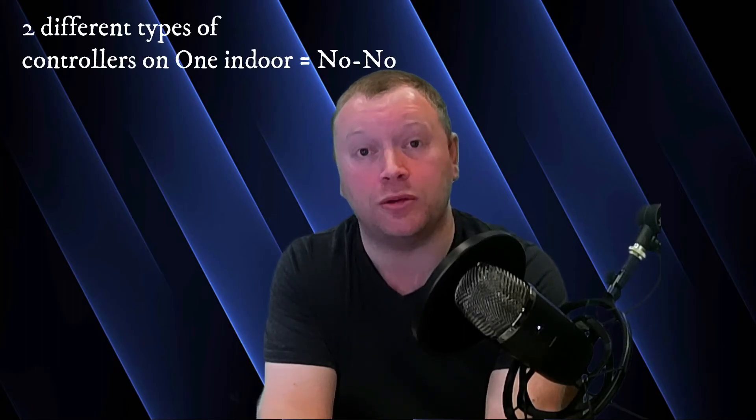Anytime a new controller comes out, I always get this question: can I mix and match different controller types on my equipment? For example, if I want a Daikin 1 controller in my great room but Daikin Madoka controllers everywhere else in my house — can I do this? Absolutely. What you can't do is put a Daikin 1 controller and a Madoka controller both on one indoor unit. But you can put a Madoka controller on one indoor unit, a different Madoka controller on another unit, and a Daikin 1 controller on a third unit. You can even weave in the Nav Controller as well — just make sure you don't have different controller types wired to the same indoor unit.